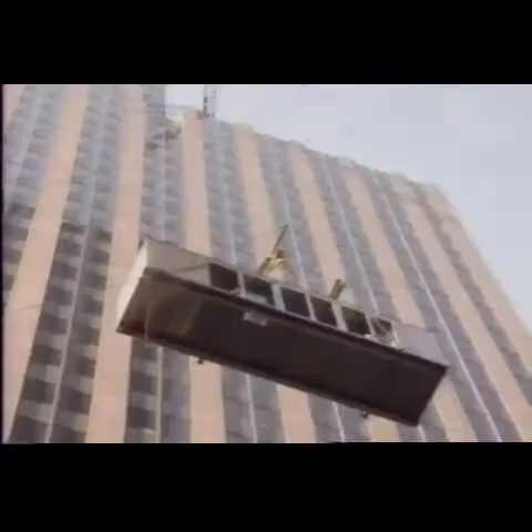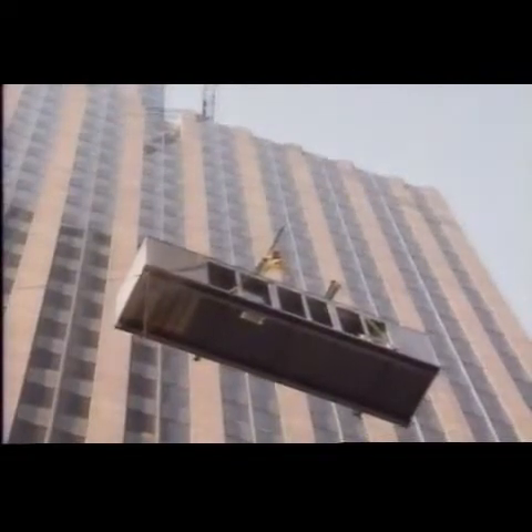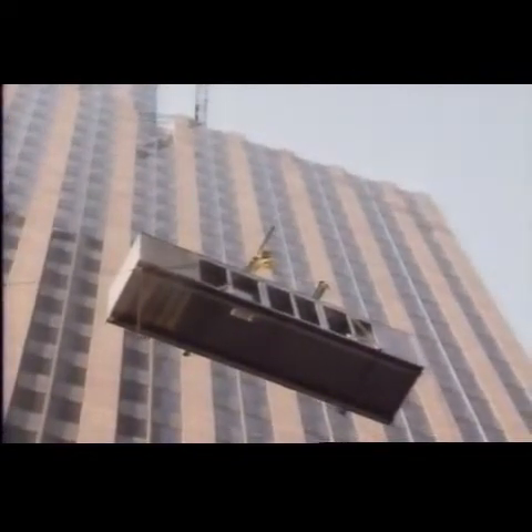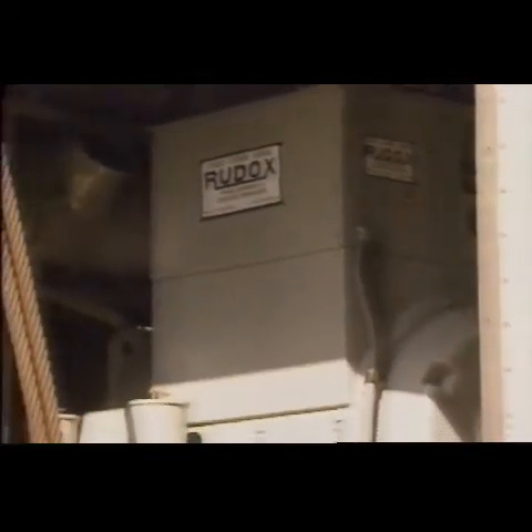The challenge? Add a virtually transparent system to an existing 50-story, 1 million square foot office tower, which can supply 6.5 megawatts of electrical power in a matter of seconds in the event of a loss of external utility power. Economic and practical limitations required the team to use the existing bus riser installed in the building and to incorporate 4 quiet 1.65 megawatt generators, a fuel system, and power control system into the building design without taking up any rentable space or diminishing the building's aesthetics.